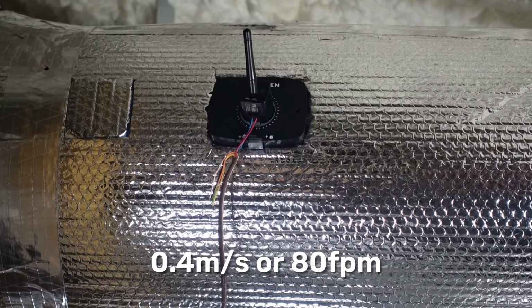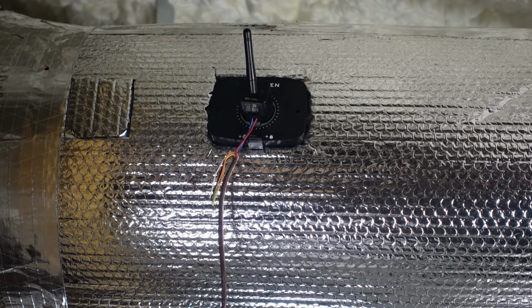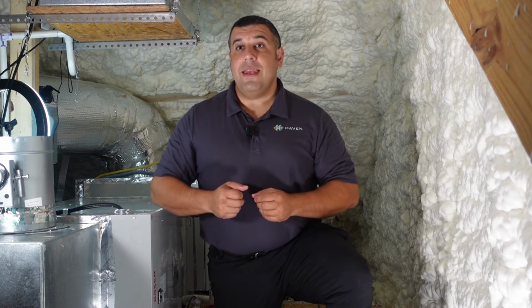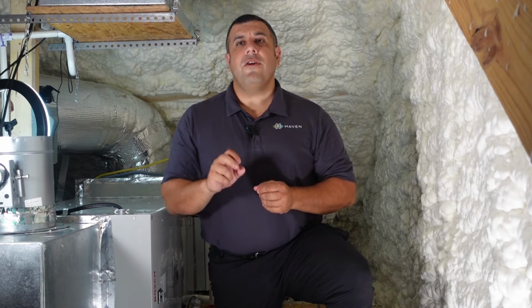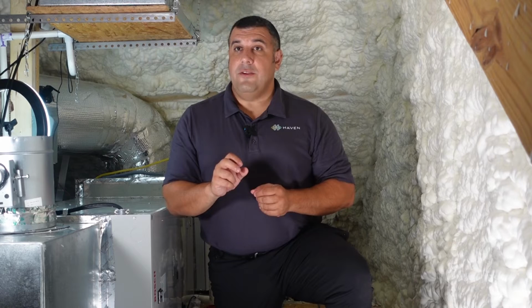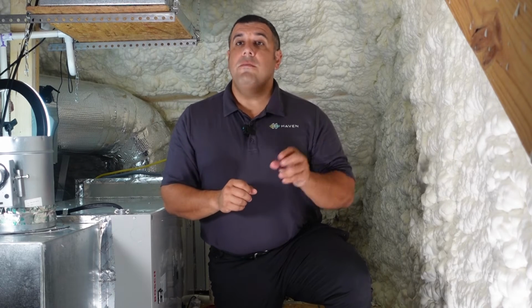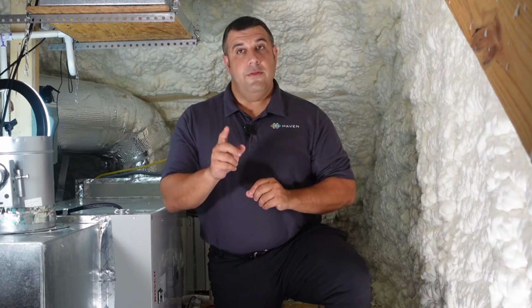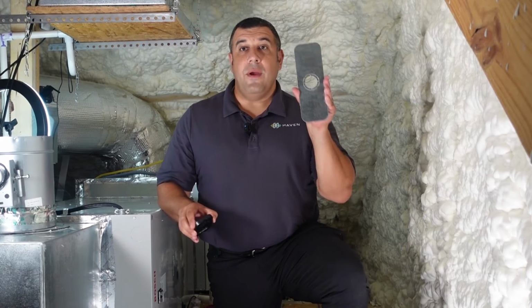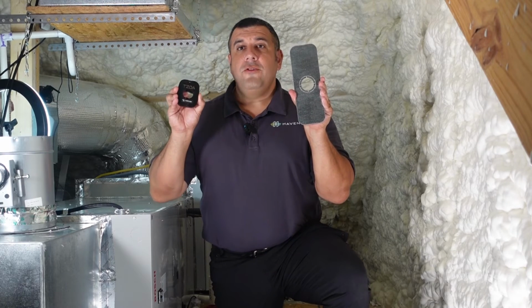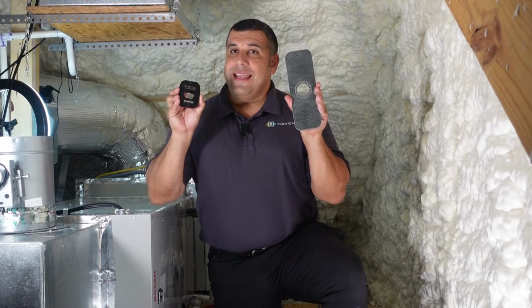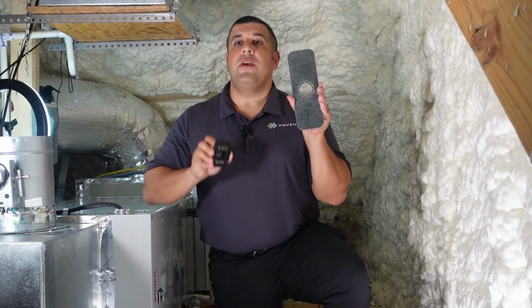Remember that the ideal airflow is above 0.4 meters per second or 80 feet per minute. If you can't achieve that in the app, try rotating the monitor a little bit more during the airflow validation process, or you may have to move the monitor to a different position in the ductwork. If you have the non-rotating version, once you find your final position, put down your phone and secure the screws in place.